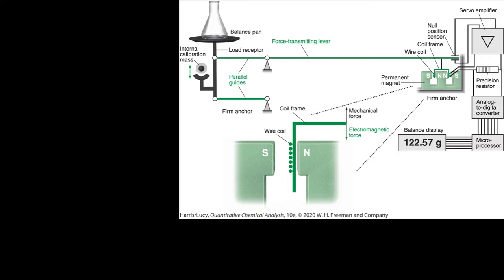And so as soon as this changes, it basically sends a signal to this servo amplifier that passes a current through this electromagnet to essentially pull the beam back down again to oppose the weight of the object you've put on the balance pan.